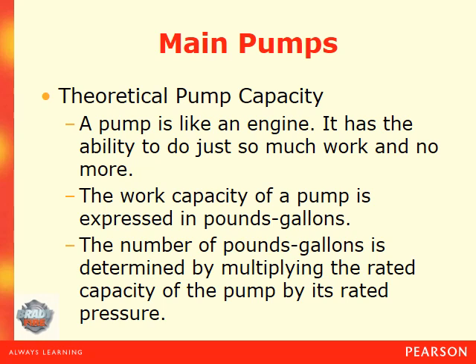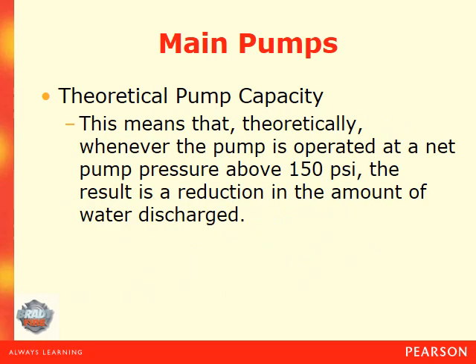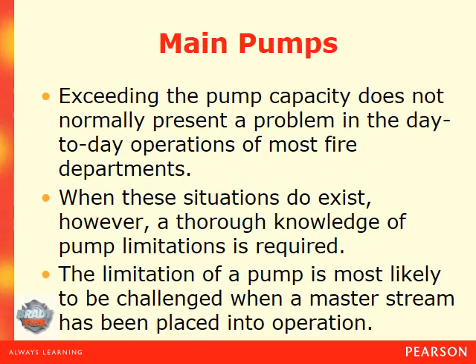Theoretical pump capacity: a pump is like an engine — it has the ability to do just so much work and no more. The work capacity of your pump is expressed in pounds and gallons, determined by multiplying the rated capacity of the pump by its rated pressure. Theoretically, whenever the pump is operated at a net pump pressure above 150 psi, the result is a reduction in the amount of water discharged. Exceeding the pump capacity does not normally present a problem in day-to-day operations, but when these situations do exist, a thorough knowledge of pump limitations is required.